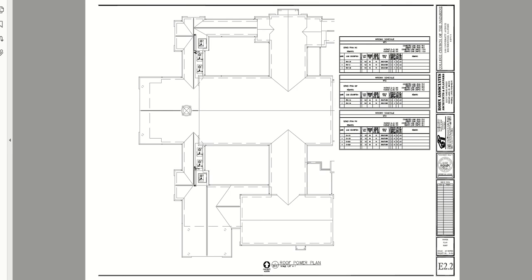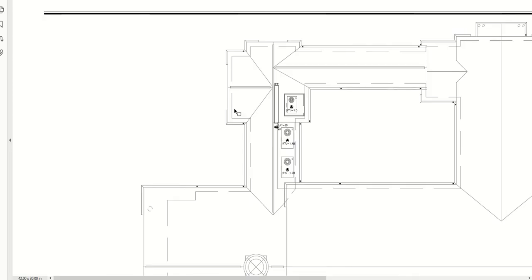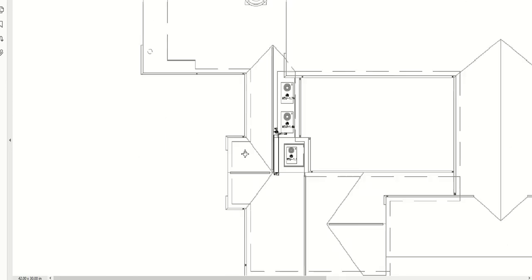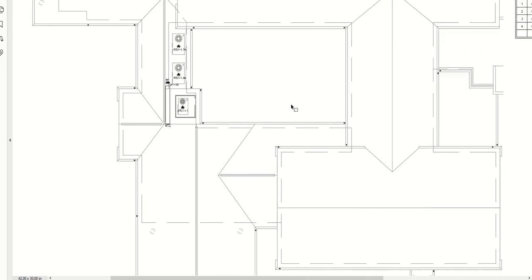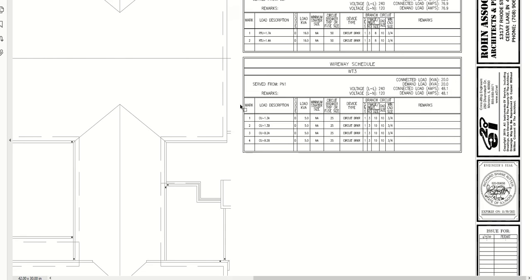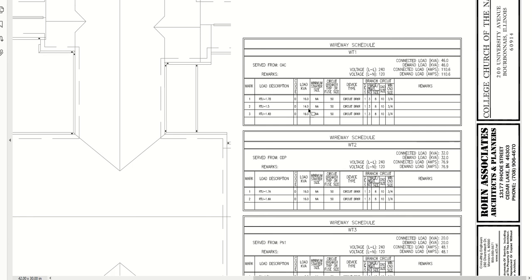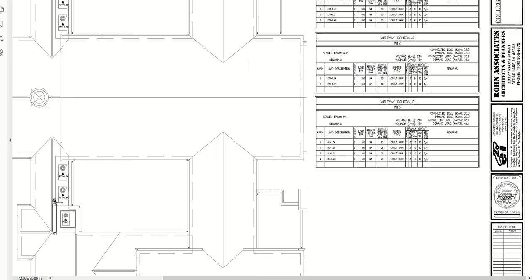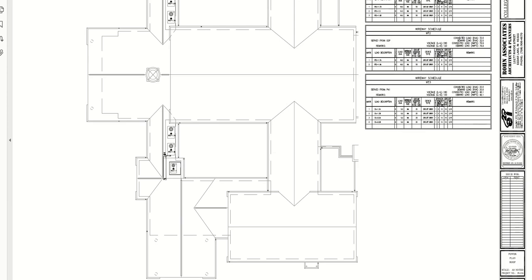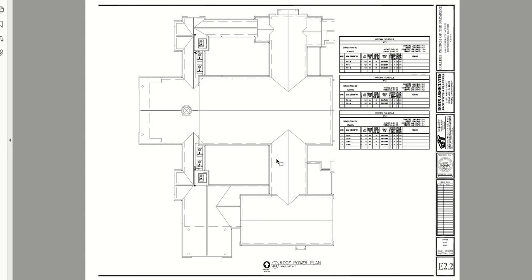On the roof, we also put some mechanical equipment. We did the same thing with wire troughs up here because of the length of the run—it didn't make sense to put a panel up there. We put a schedule for these wire troughs showing what loads are tapped off of each. This helps us size the feeder to each wire trough. We need at least a 110 amp feeder here, probably an 80 amp feeder here, and at least a 50 or 60 amp feeder to each of these troughs. We show what comes from each trough as well.